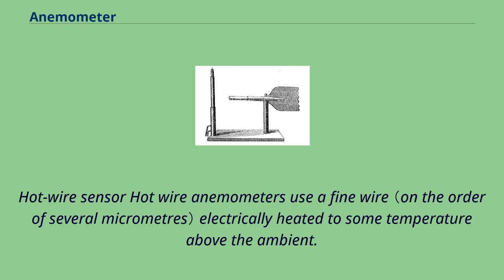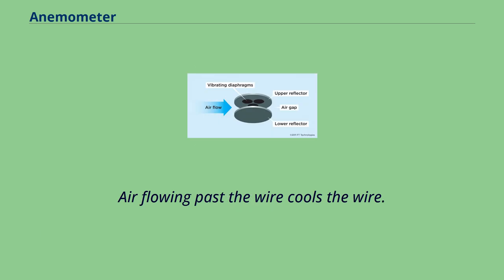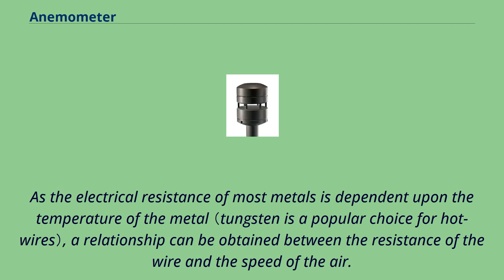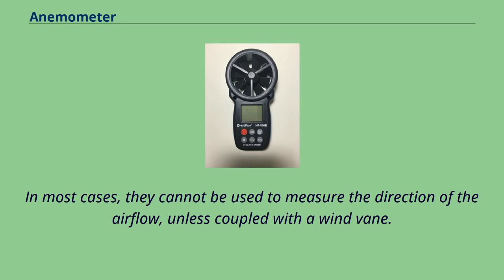Hot-wire anemometers use a fine wire electrically heated to some temperature above the ambient. Air flowing past the wire cools the wire. As the electrical resistance of most metals is dependent upon the temperature of the metal, a relationship can be obtained between the resistance of the wire and the speed of the air. In most cases, they cannot be used to measure the direction of the airflow, unless coupled with a wind vane.